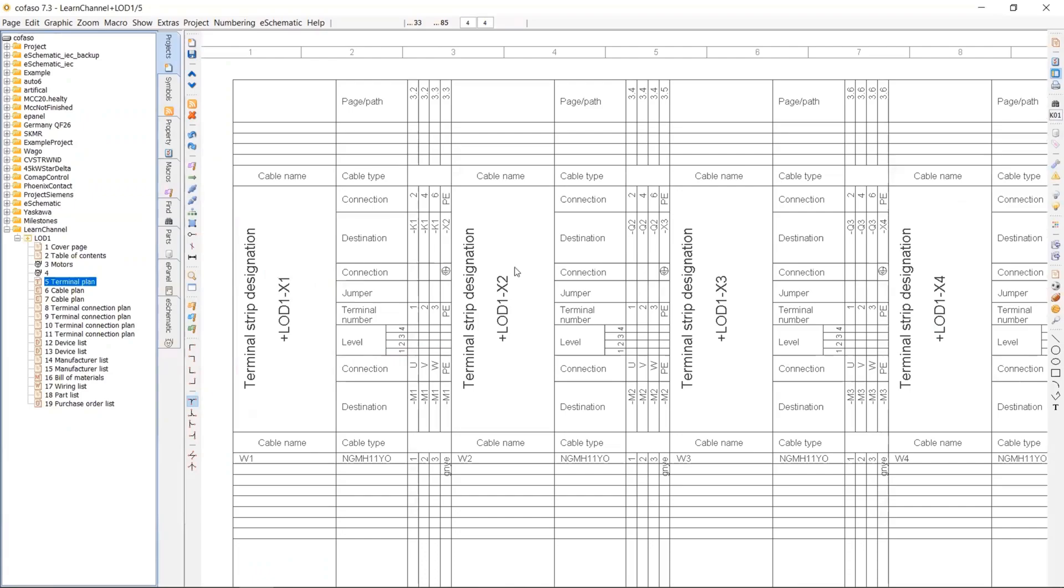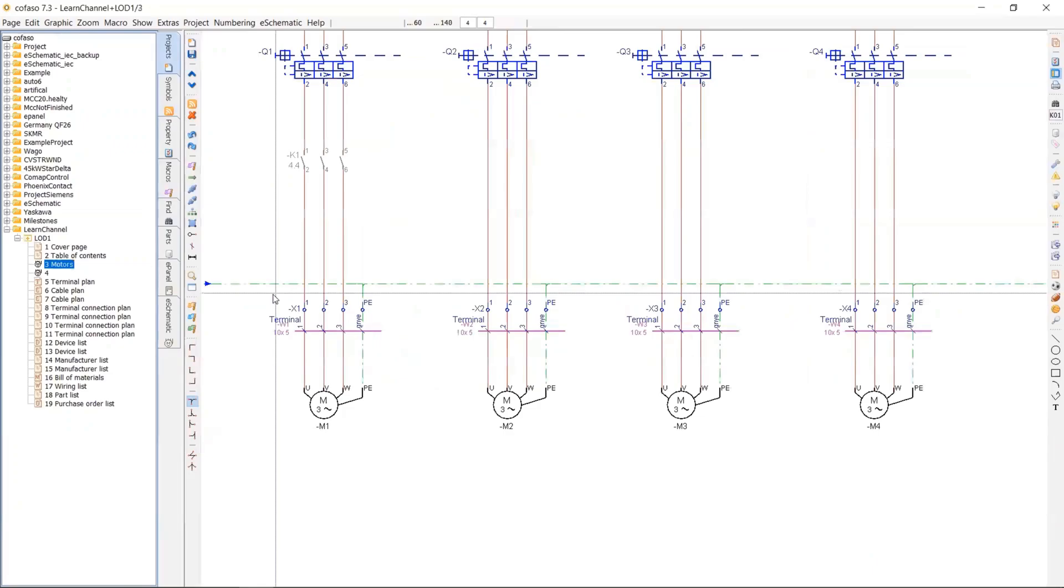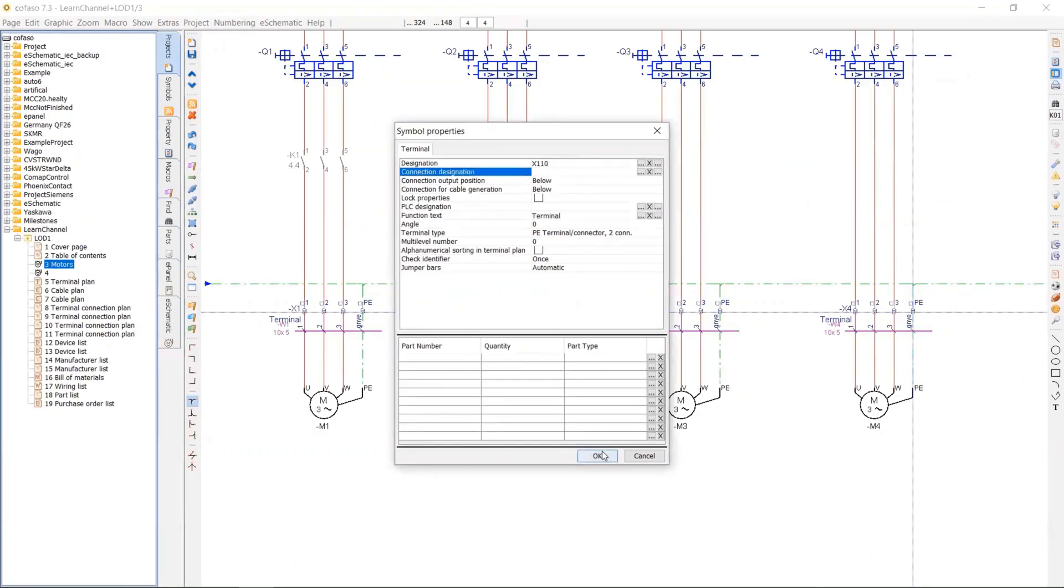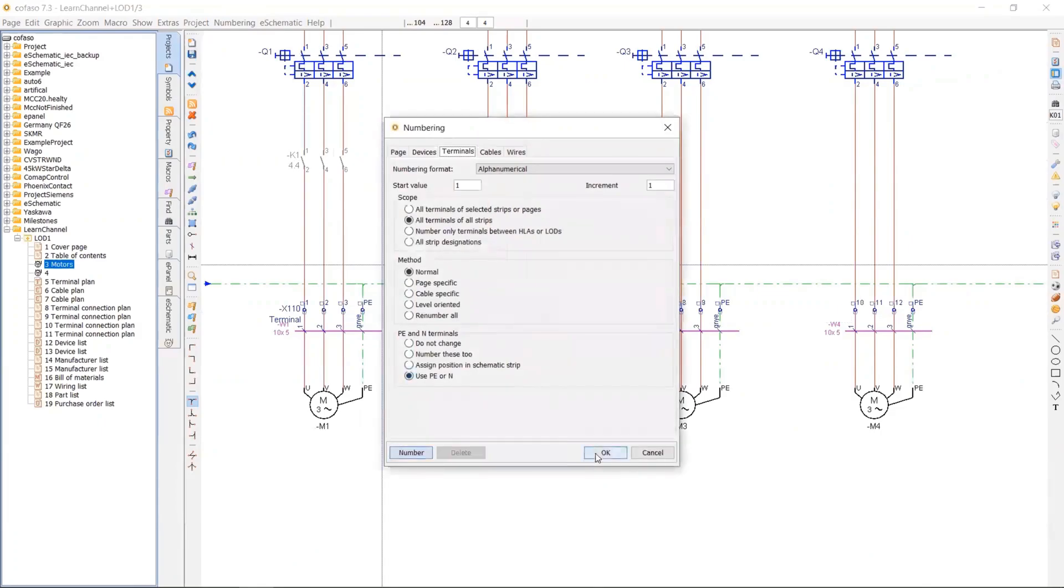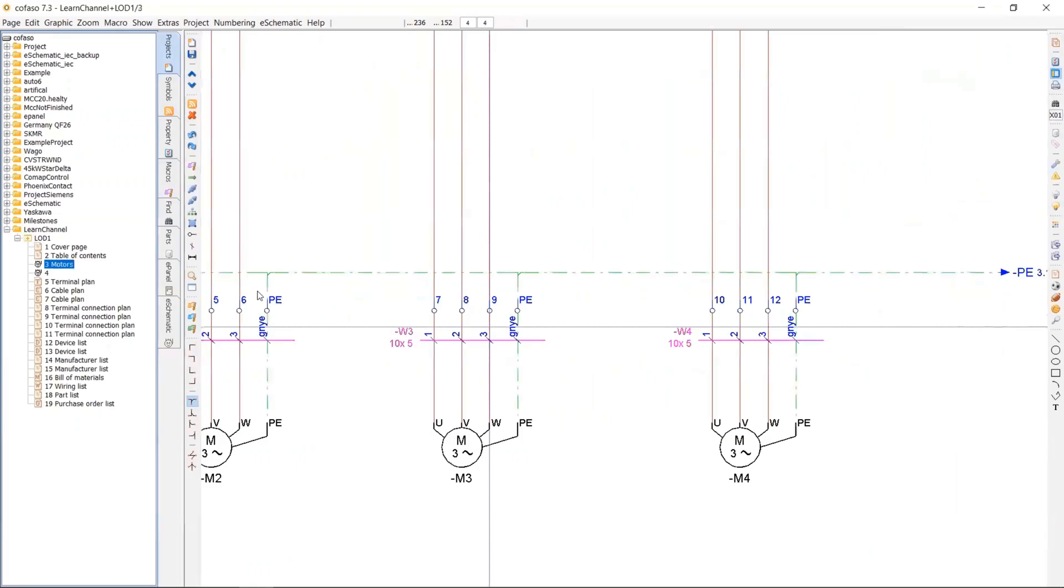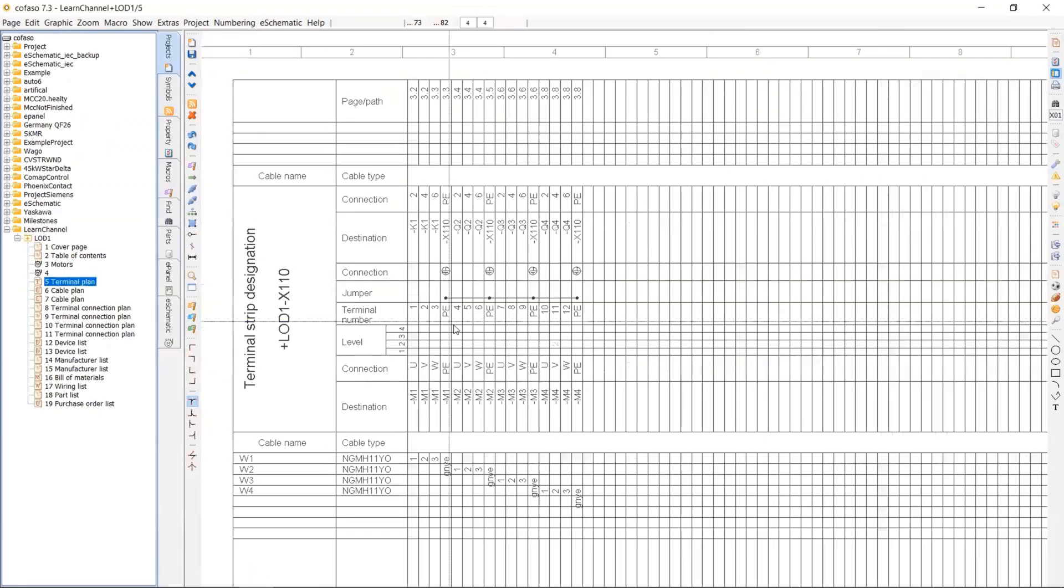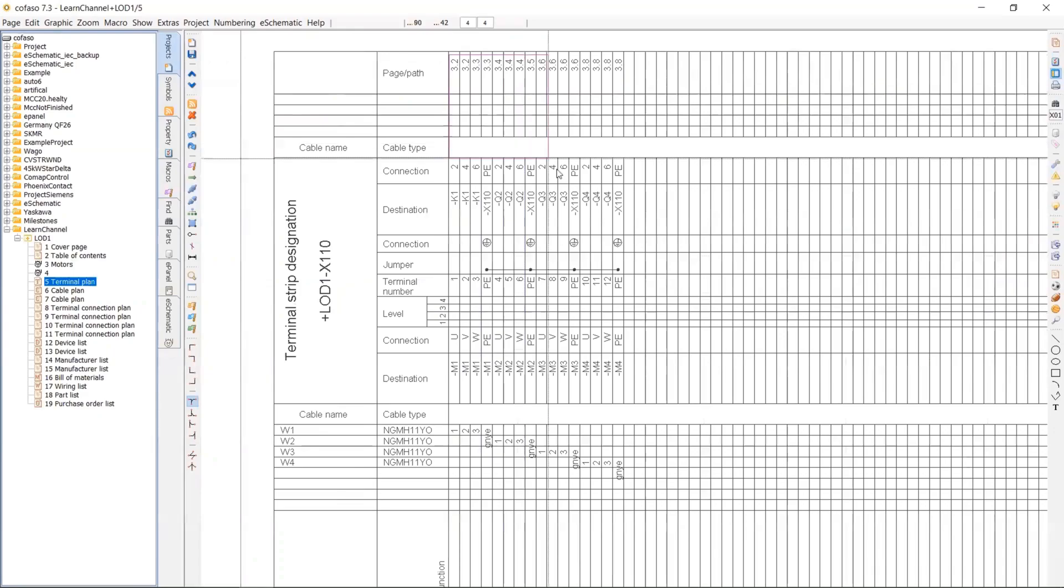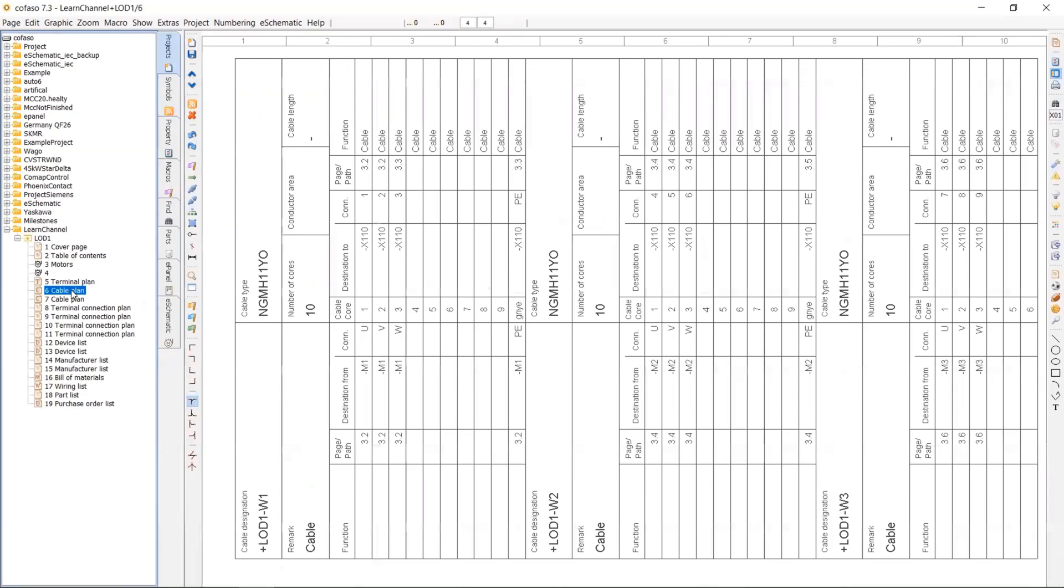So I have four terminal strips in my terminal plan. And I will make a change here instead of four terminal strips, I want to have only one terminal strip. And let's number the terminals. Then here, as you can see, the system updated in the terminal plan to change immediately. So now I have 16 terminals altogether in under X110.